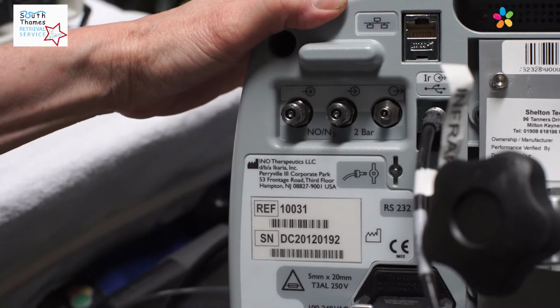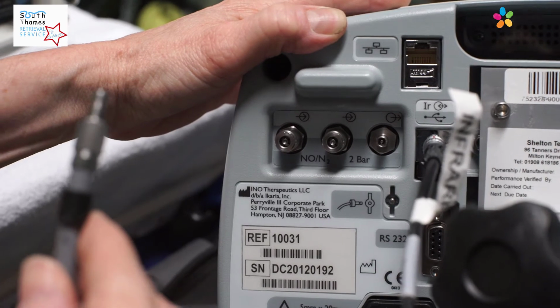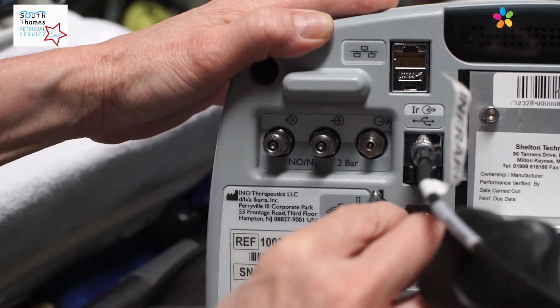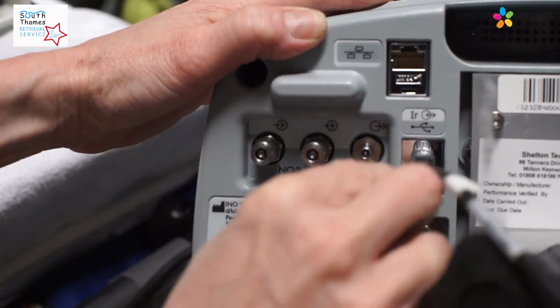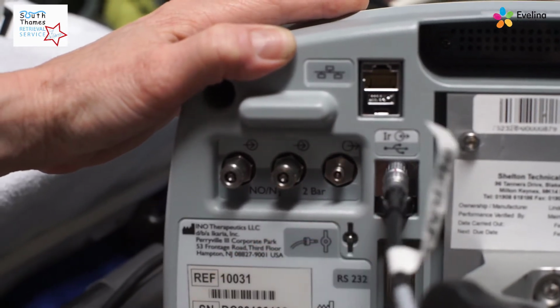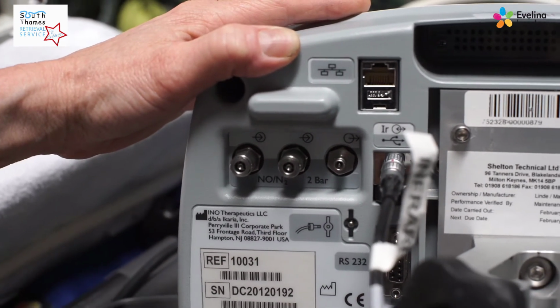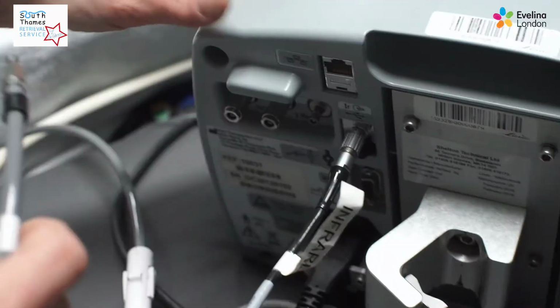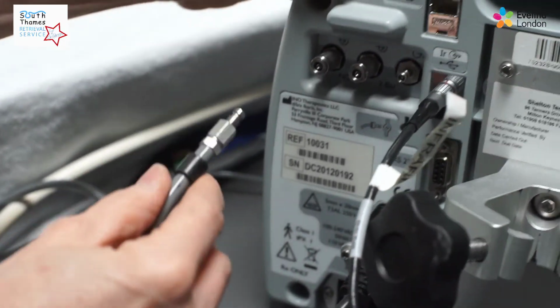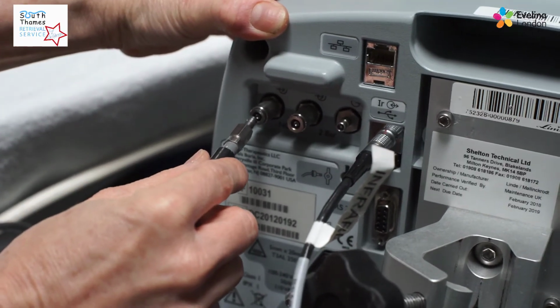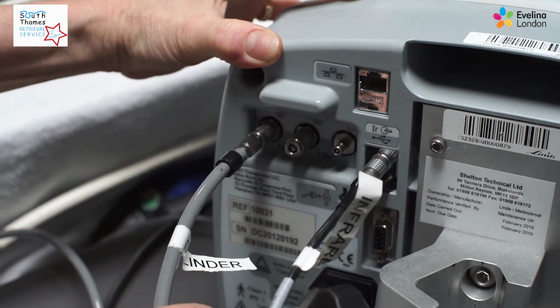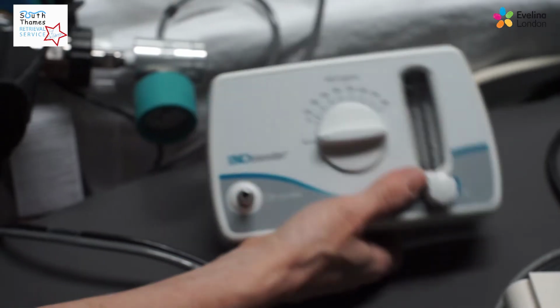So take the grey portable nitric lead, which is attached to the cylinder head, and press the lead into the nitric purging point and hold until the gas has escaped. This should take about 1 to 3 seconds. If it's longer, just check that you've turned the cylinder off fully. Connect the grey portable nitric lead to the back of the Inomax marked cylinder 1. Reconnect the grey nitric bagging lead from the blender to the back of the monitor next to the infrared lead.